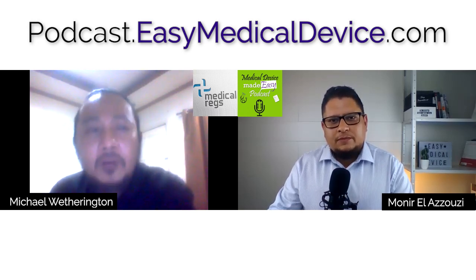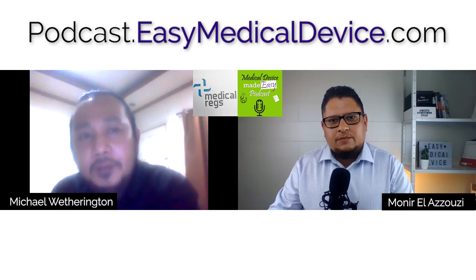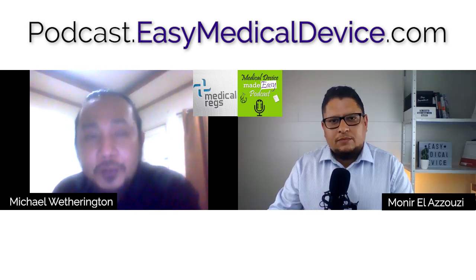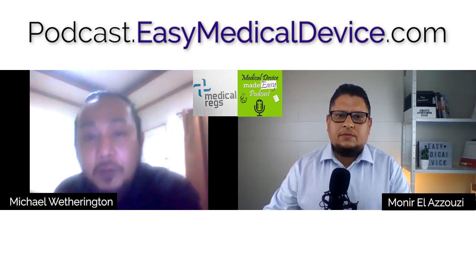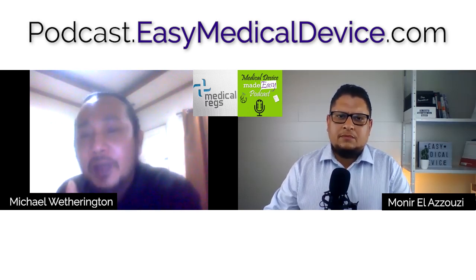Yeah, actually, it all goes back to starting it off right. So you have a medical device that you want to develop. Based on your conceptual idea or early design stage, you should be able to identify what standards would apply to you. And by reading the scope of each of the standards that you identify, you determine whether it gets fed through your design inputs. So for example, like you mentioned, IEC 60601, you have to read the scope of that. If you fall within that scope, then you design to the requirements of that.